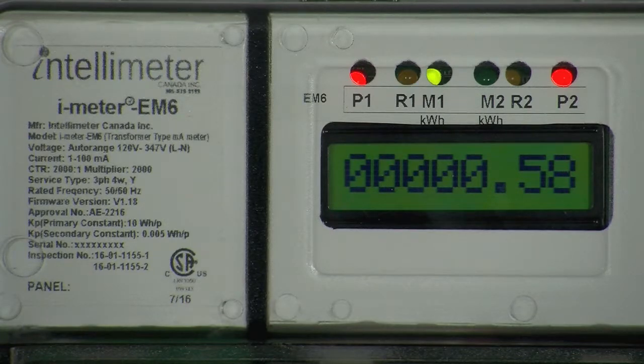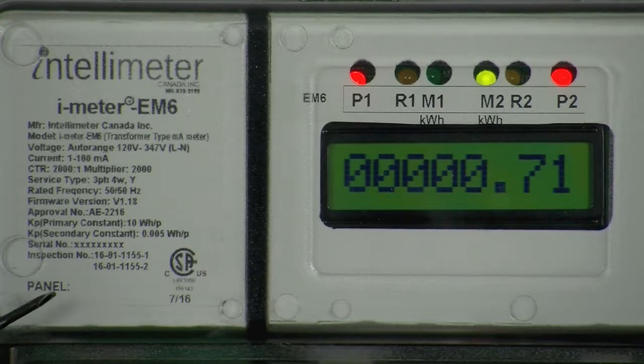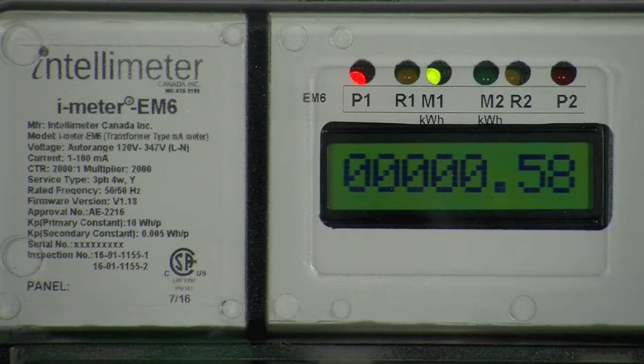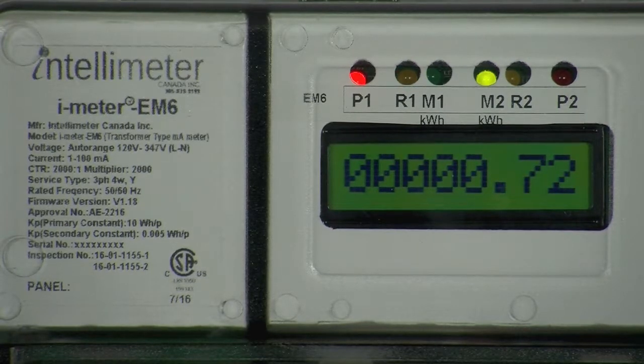We're going to repeat the phase test that was covered earlier in this video and ensure that line 1 in our reference voltage is on phase A and that CT1 is installed on phase A as well. Document your findings and if needed, make corrections accordingly. All of the same goes for line 2 for CT2 on phase B and line 3 for CT3 on phase C.